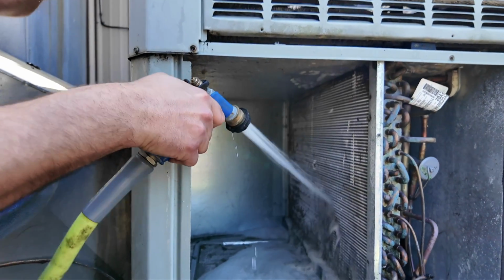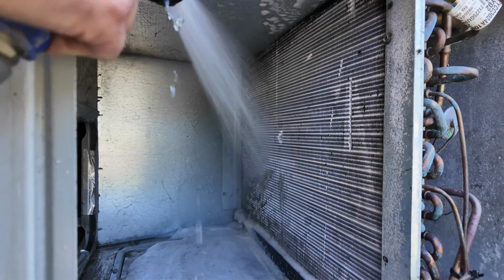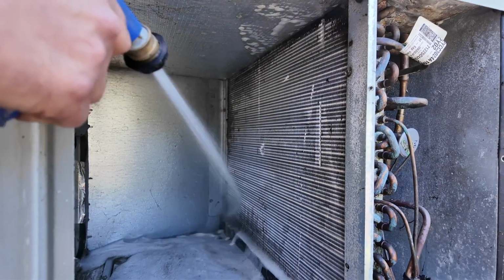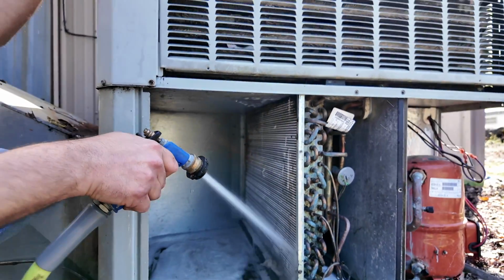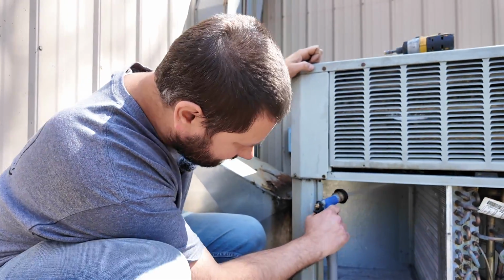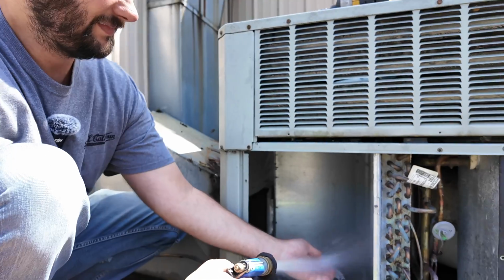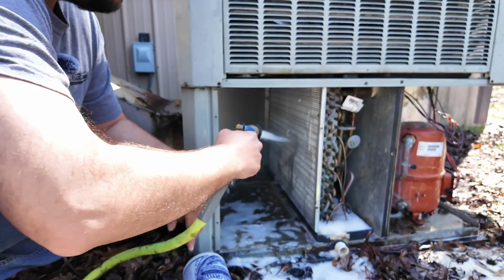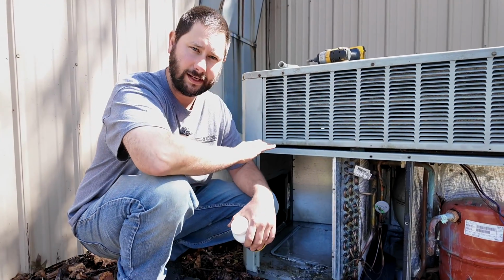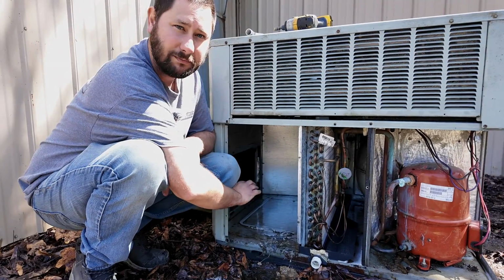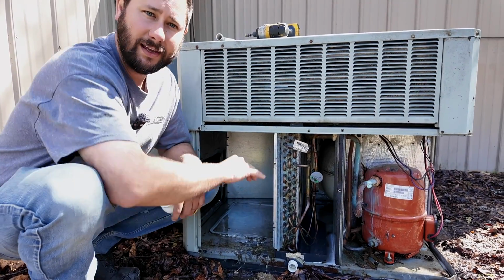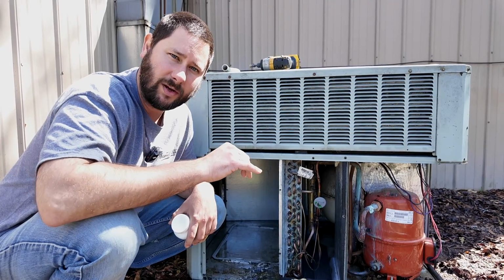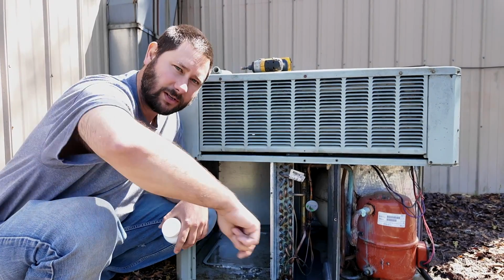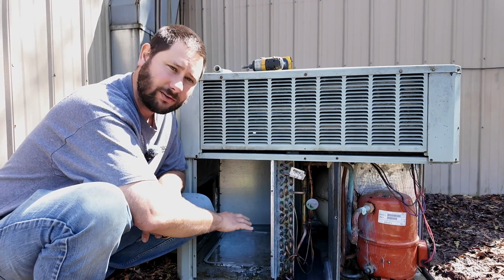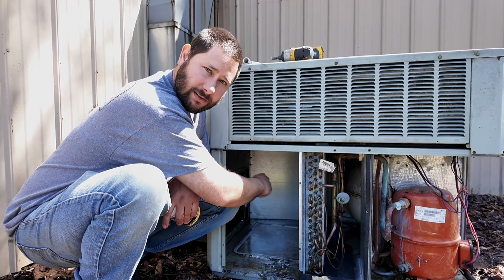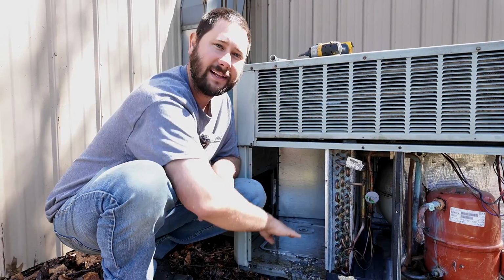Look at all that disgusting junk coming off there. Having a vacuum cleaner is very helpful during this stage. That is some dirty water. Now this coil is nice and clean, and before we had a big puddle of what looked like mud water, now the water is clear. If you've got a vacuum, definitely bring a vacuum with you. It's great for using in outdoor units where you can reach in there and suck everything out. It's also great for using in sections like this where you can suck all that water out instead of having water stay inside the unit.